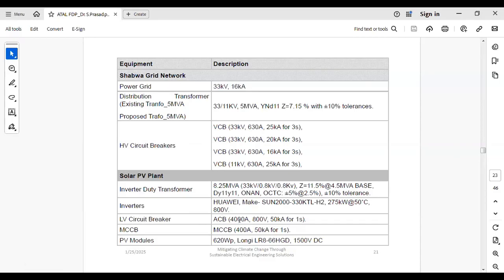At the solar PV plant, the LV circuit breaker is an ACB, air circuit breaker, of 4000 ampere at the LT panels. So at the low voltage level, at 0.8 kV, we are using ACB and MCCB, but at a high voltage level we are using vacuum circuit breaker, VCB, or SF6 circuit breakers, basically used for high voltage systems. So the same plant I have considered and conducted the load flow and short circuit study.